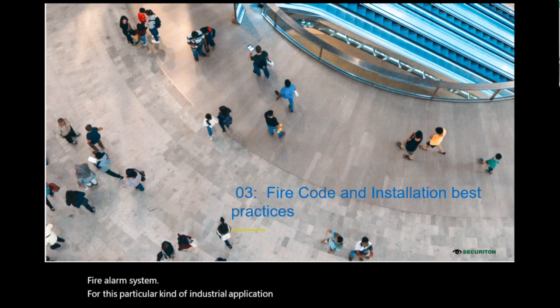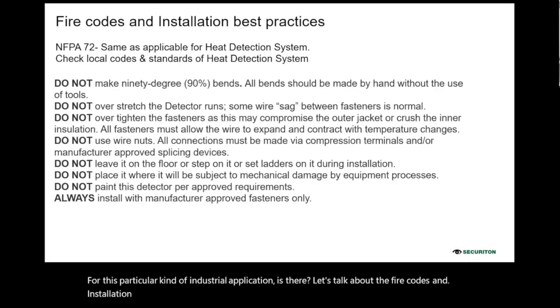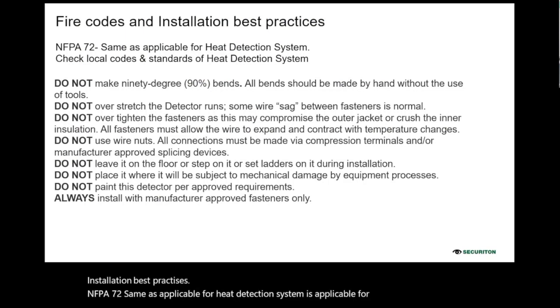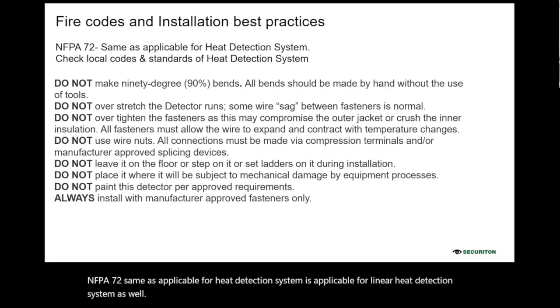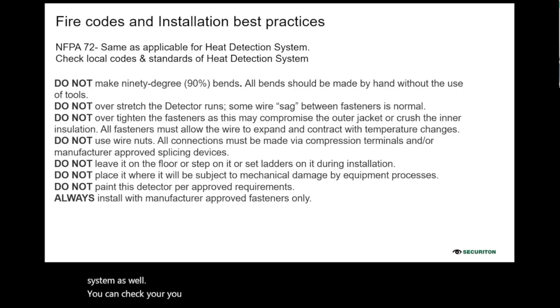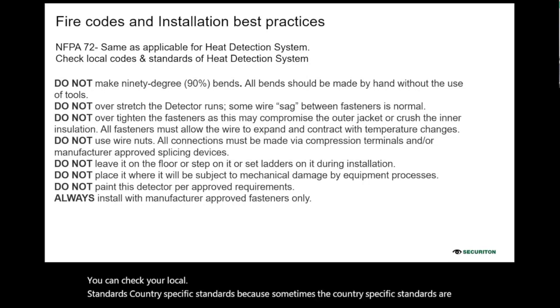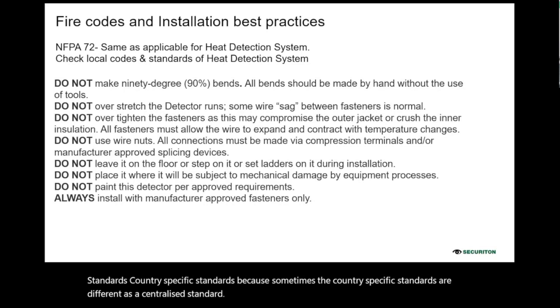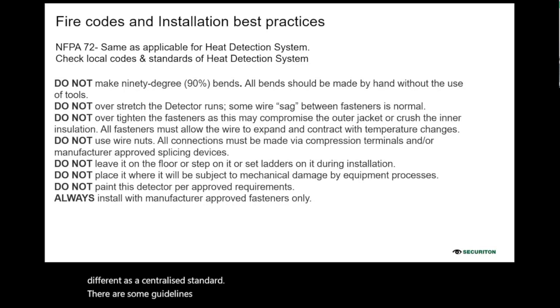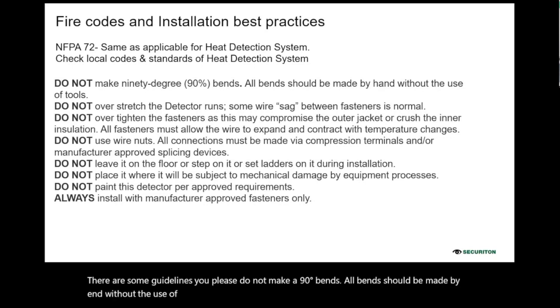Let's talk about the fire codes and installation best practices. NFPA 72, same as applicable for heat detection system, is applicable for linear heat detection system as well. You can check your local, country specific standards, because sometimes the country specific standards are different from a centralized standard. There are some guidelines. Please do not make 90-degree bends. All bends should be made by hand without the use of tools if you are installing linear heat sensing cables. Do not overstretch the detector runs.